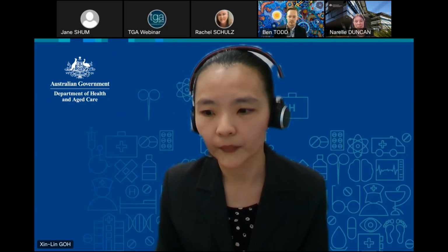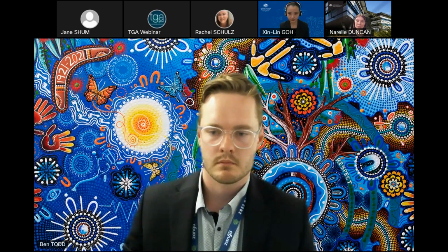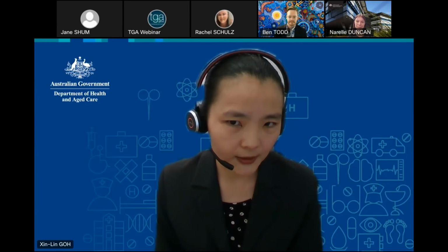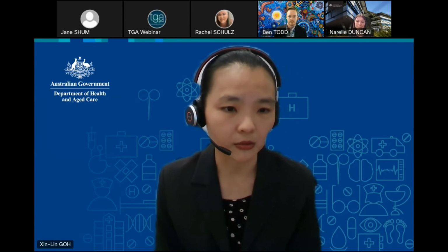Thank you, Sinlin. Last question. If the intended purpose is changed along with the classification of the device, what application will I need to submit? It will require a new application for inclusion because the classification of the device has changed. So that change will render it a new kind of device. So it will be a new application for inclusion.